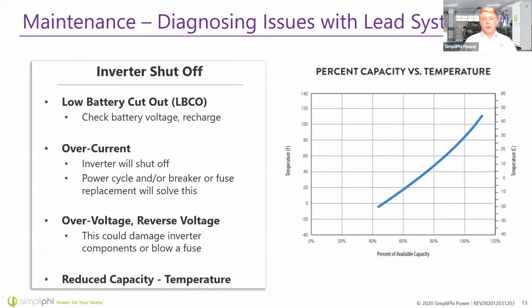Here's another issue you could be seeing with your system, even lead acid or even otherwise. You may be seeing a low battery cutout event. If your inverter has shut off, that's one of your things you may be seeing. So if your inverter shut off, first, don't just go and throw those batteries out and replace them. Let's troubleshoot this first. So you've got the potential that a low battery cutout event happened. Make sure to check the voltage of the batteries, and if they need it, recharge them.